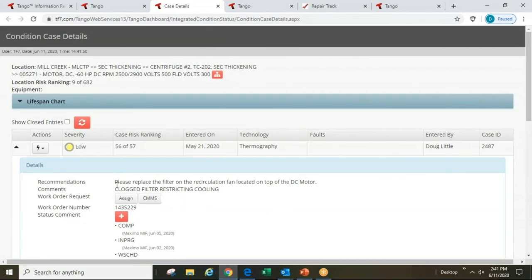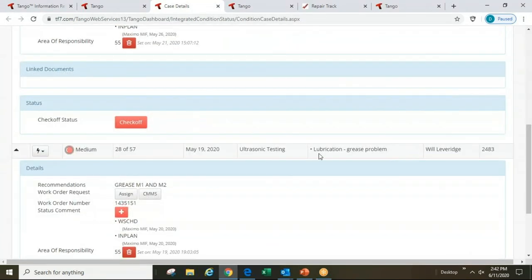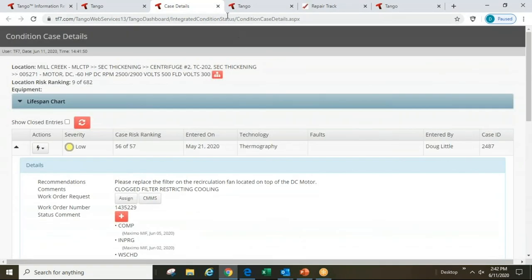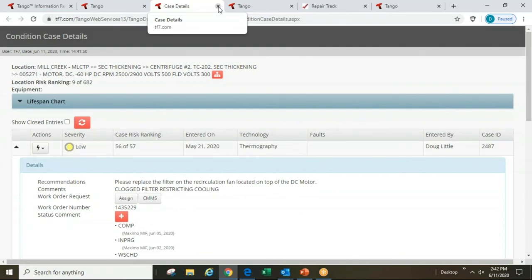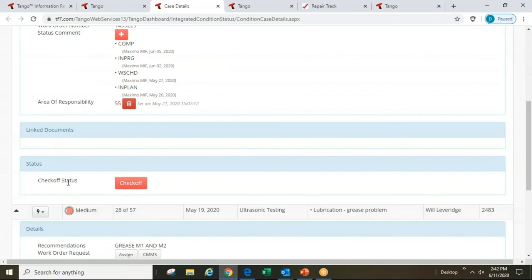Looking at the details with one click: a clogged cooling fan on the end of the DC motor came from the thermography finding — too much delta-T in heat — and the ultrasonic technician believes he's found a grease problem from lubrication. This gives work planners and people involved in a REDS meeting the details they need to discuss when these two work orders are actually going to be closed.